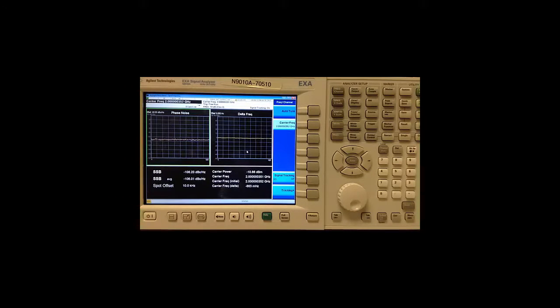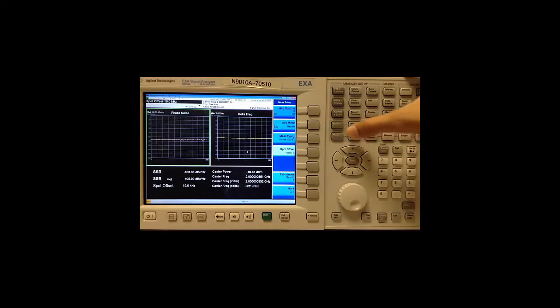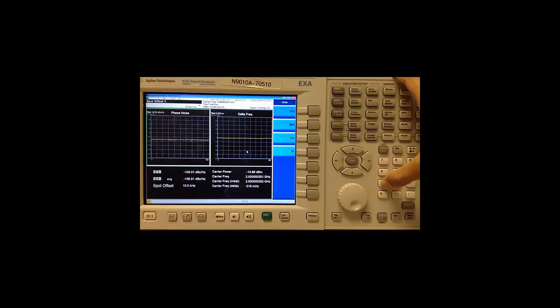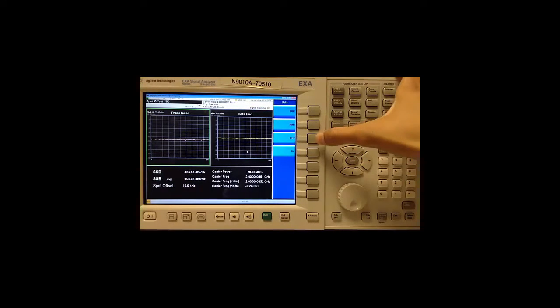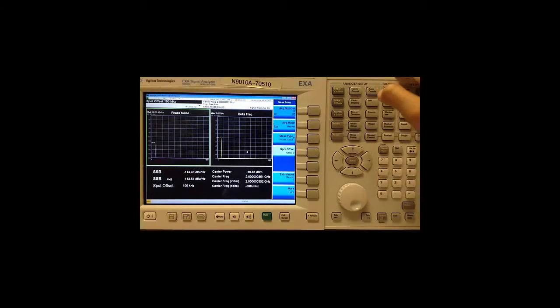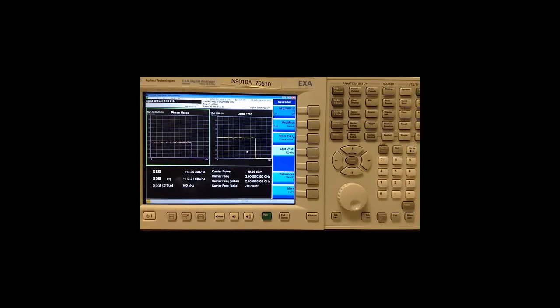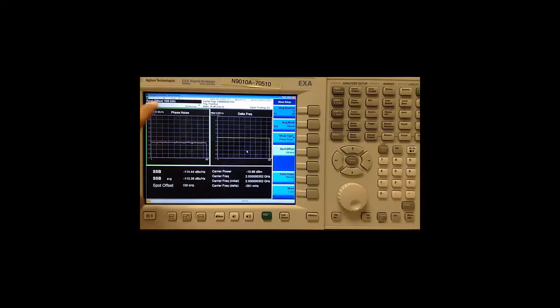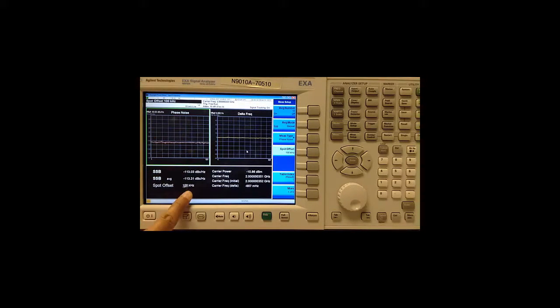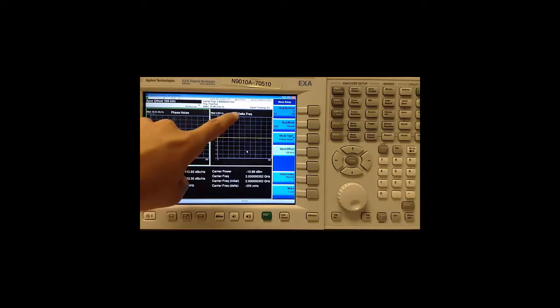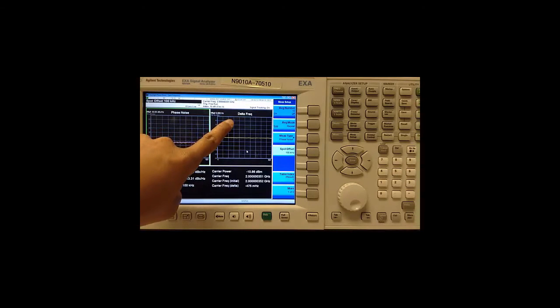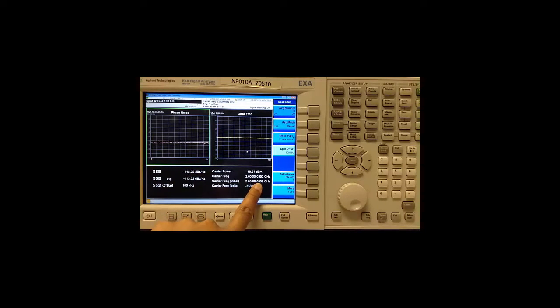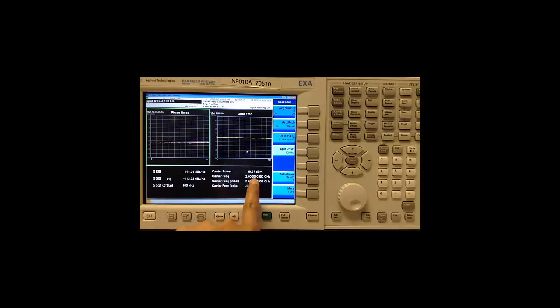The spot frequency measurement provides a time domain view of phase noise measured at a specific offset frequency from the main carrier signal. We can choose the desired offset under measure setup and then spot offset. I am going to choose 100 KHz as an example.